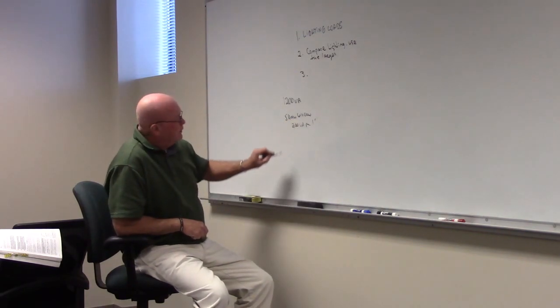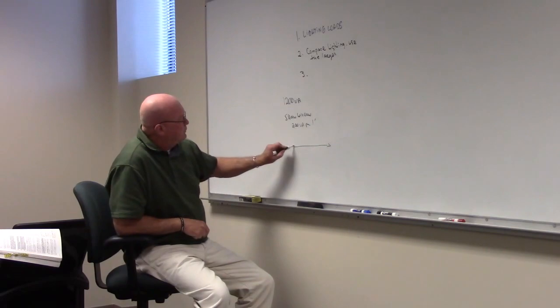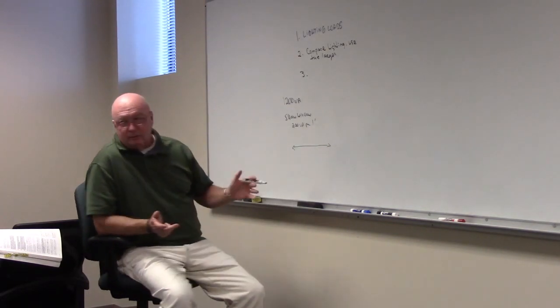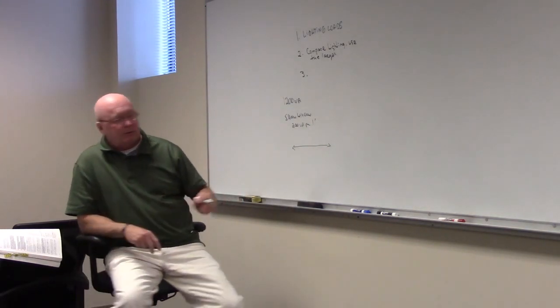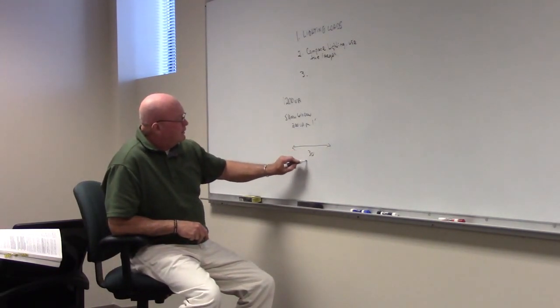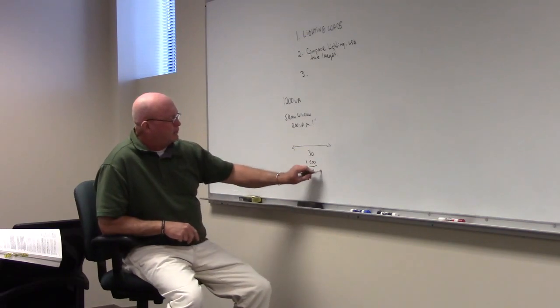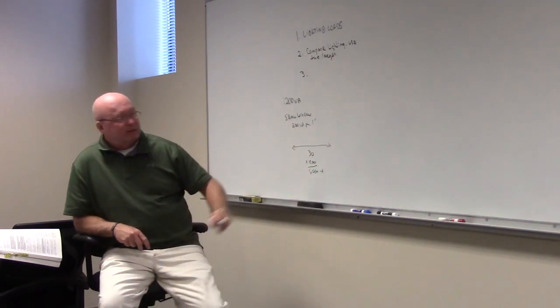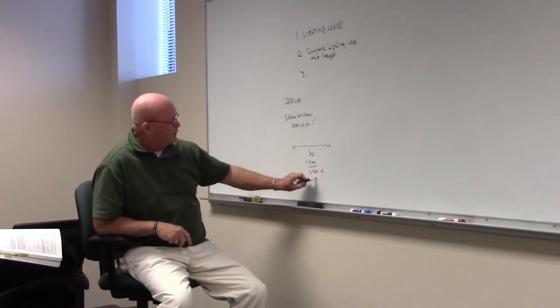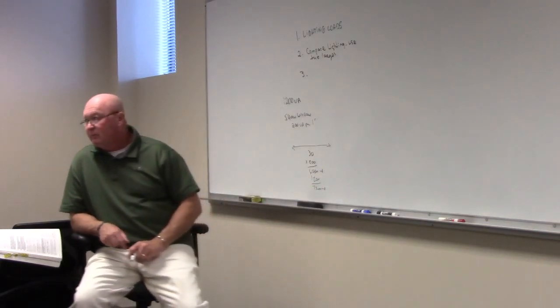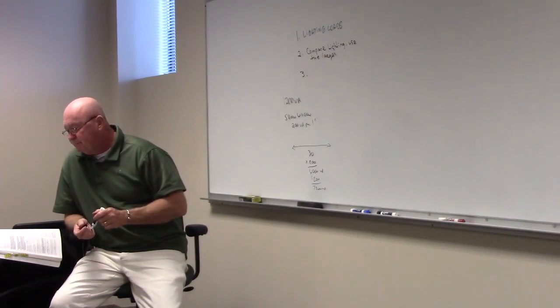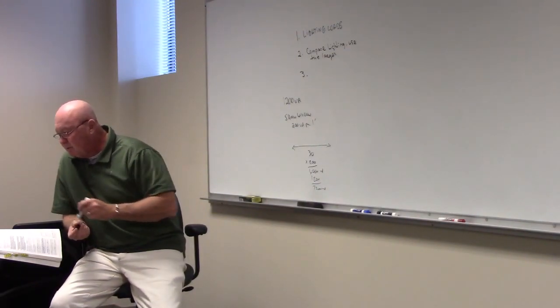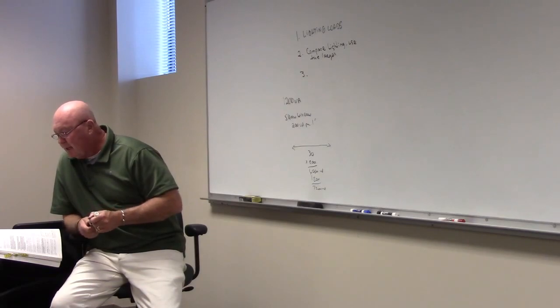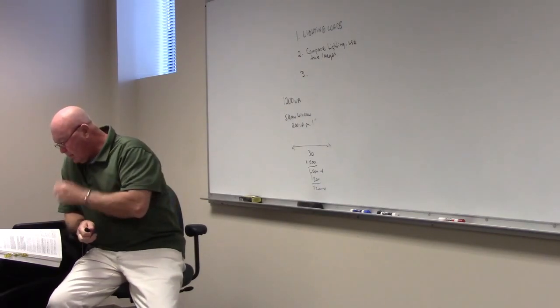So say we had a 30-foot building across. You have to take the dimensions of the building, so 30 feet across. 30 times 200 would add 6,000 volt amps to that load. And if it has a sign, we're adding another 1,200, aren't we? So that's 7,200 volt amps right there up front in a store. Okay. That's just some of the other things. Let's see. The track lighting, 220.43.